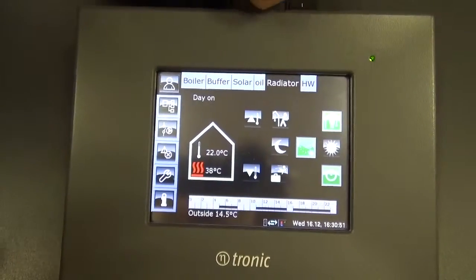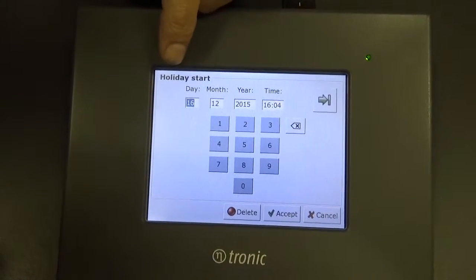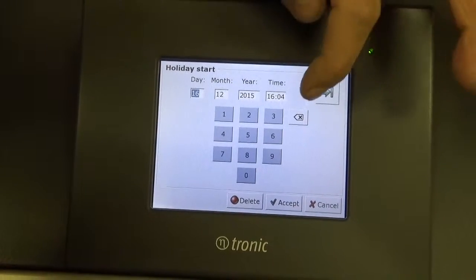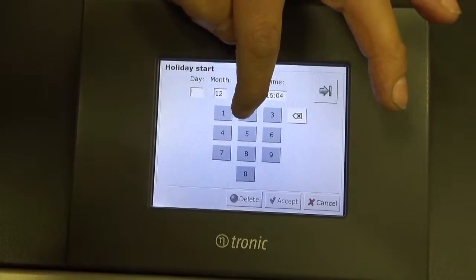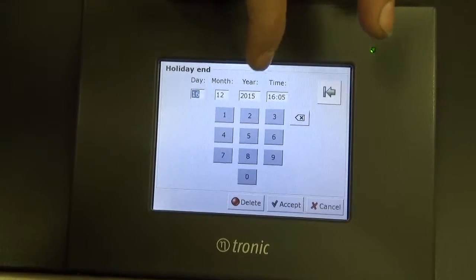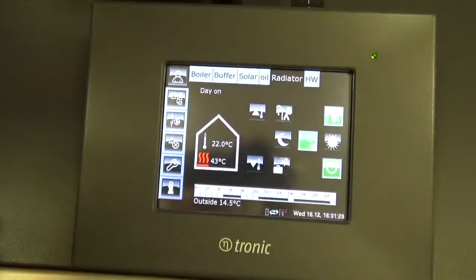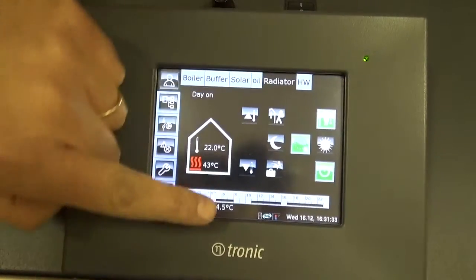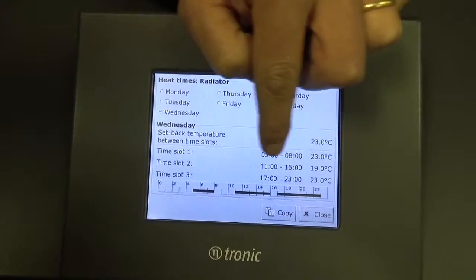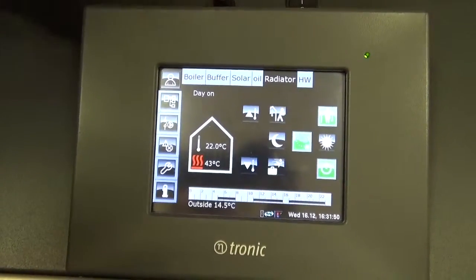Another function on the heating circuit screen is holiday mode. If we press on holiday mode we can set the dates when we go on holiday and also set the date when we come back, so the heating will return to normal when we arrive home. We can set the departure date — say the 24th — and come back on the 30th, then accept those dates. Between those dates the heating will set back to setback mode, which is the temperature used when there isn't a time slot active — in our case 19 degrees. So the heating will stay at 19 degrees from the 24th of December through to the 30th of December.